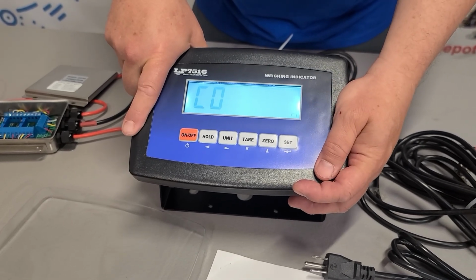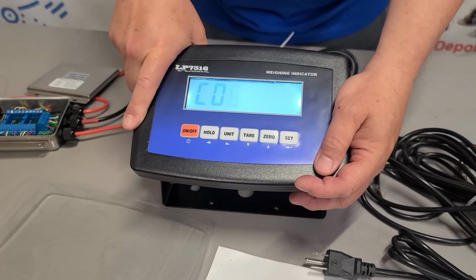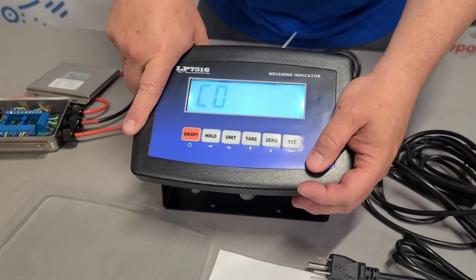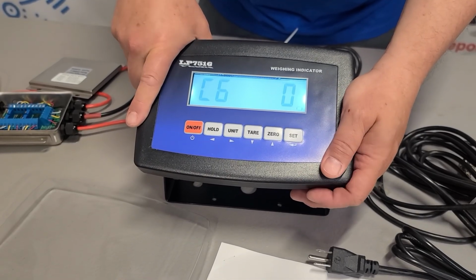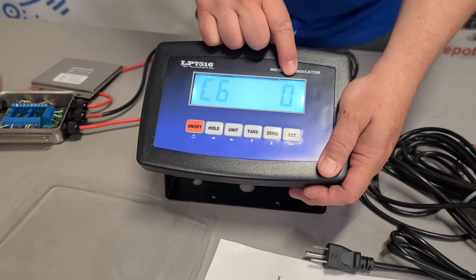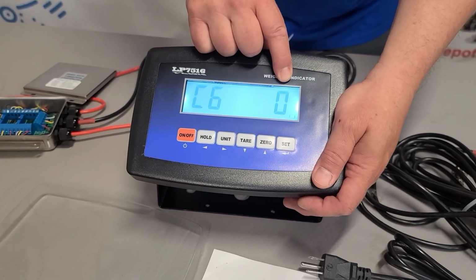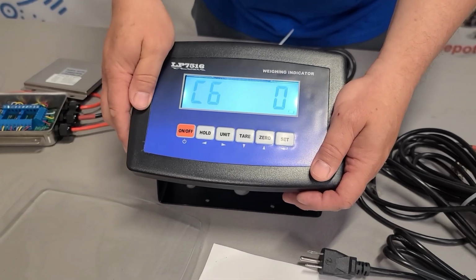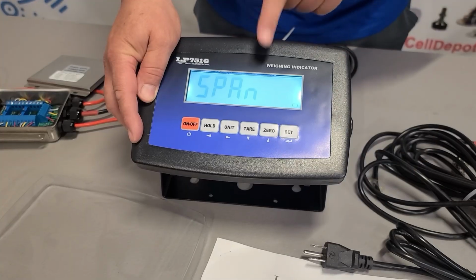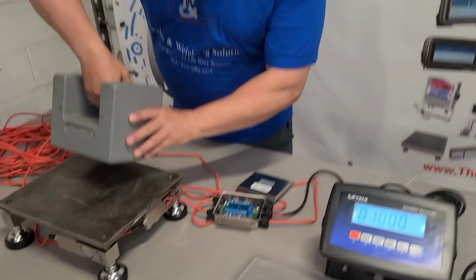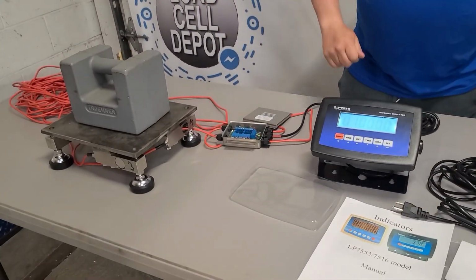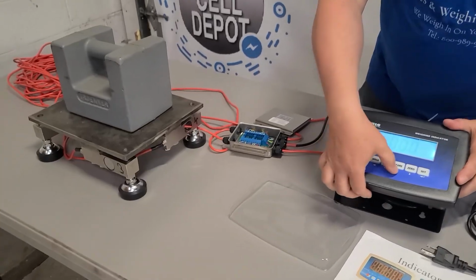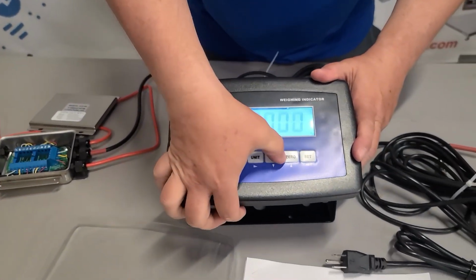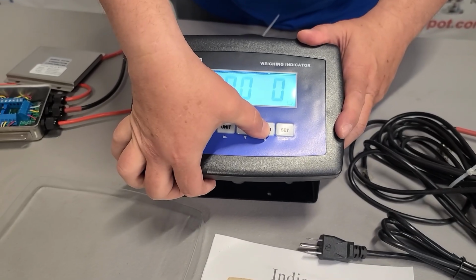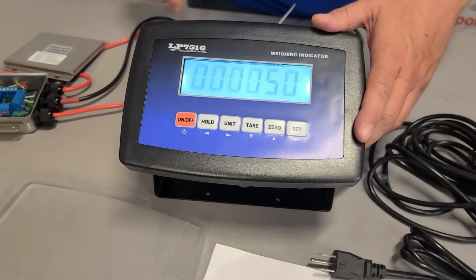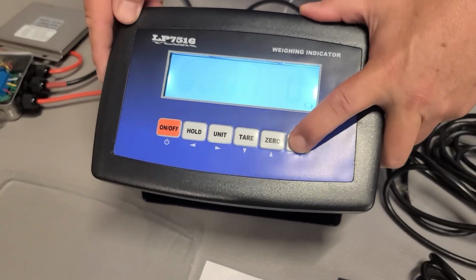Press enter, it goes to C06. Now we actually have to have some weight around near us to use. Again, as soon as you hit set, it's going to say 0 because it also wants to use the last calibration that you had in here. We're going to change that to 1 because obviously we want to calibrate. It's going to show you span. We're going to put the weight on it. We know it's 50 pounds. So we're going to change that 10,000 to 50. We're going to use the arrow keys. It says 50. When it says 50 and our weight is on the platform, we press set.